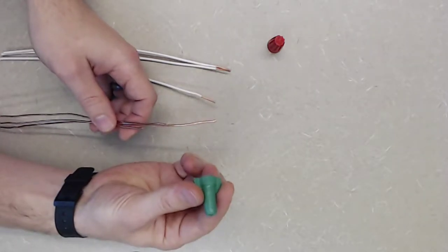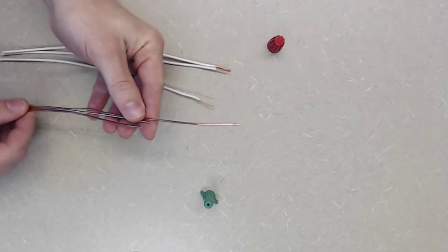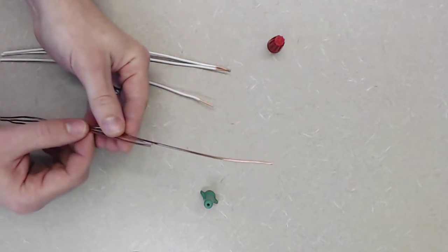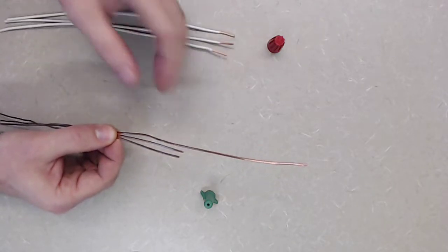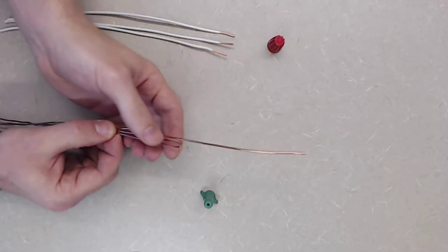So using these ground wire nuts, the key here is that you keep one wire longer than the other two or three, but the ones that you have you want to keep them the same height - the ones that are shorter.